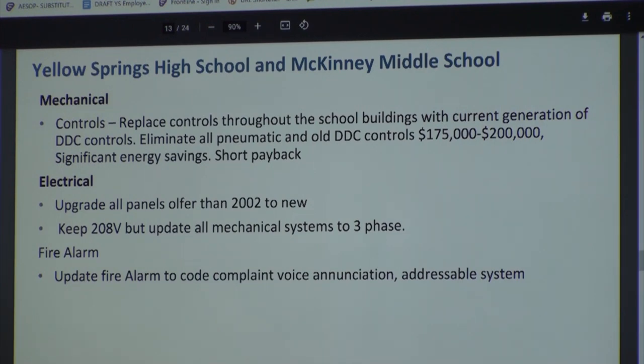Electrical, I recommend you upgrade any panel that's older than 2002. We had a big debate over 208 volt versus 480. There is no way going to 480 pays for itself in any lifetime unless you're doing a new building. So keep the 208. Some of the equipment is single phase, it ought to be three phase. Everything should be three phase that's over a certain horsepower. But those heat pumps are all single phase, I would make those all three phase. The 208 is here to stay, there's really nothing you can do, and it's not really causing you a penalty. It's just over time the equipment manufacturers are slowly not making it.